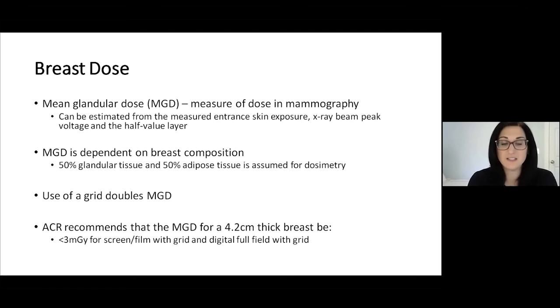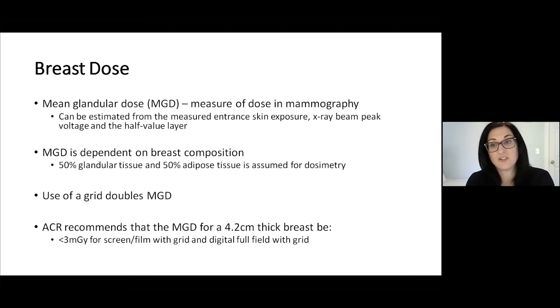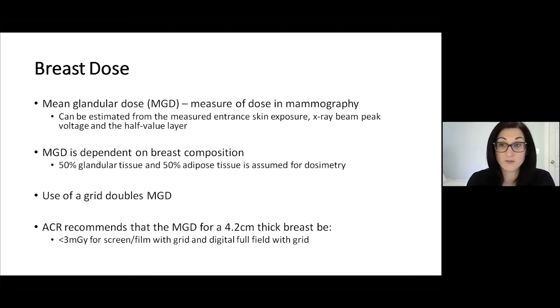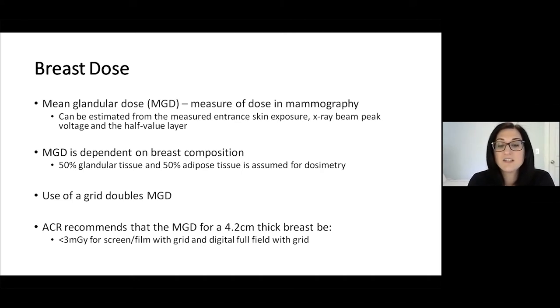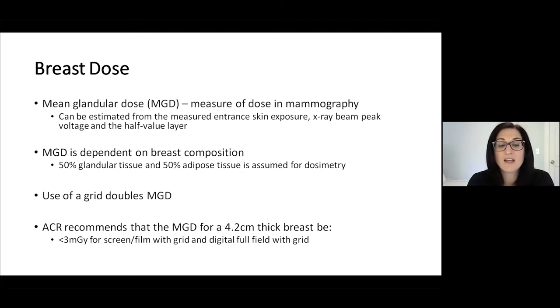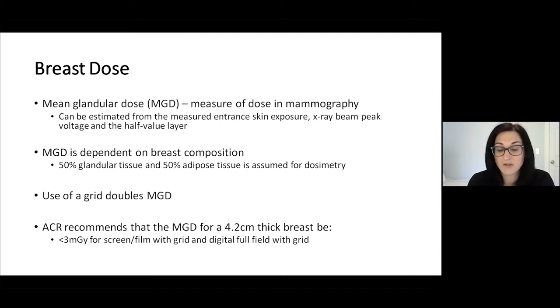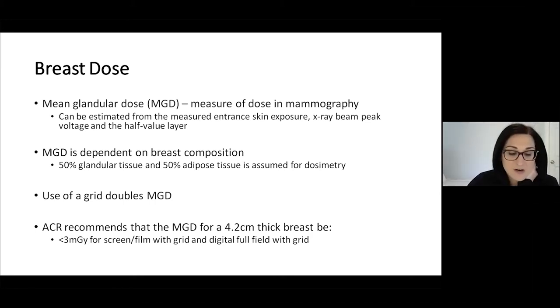Using a grid doubles the mean glandular dose, but as discussed, it improves image quality and contrast. The ACR recommends that the mean glandular dose for a 4.2 centimeter thick breast be less than 3 milligray — and that's for either film screen with a grid or digital full field with a grid.